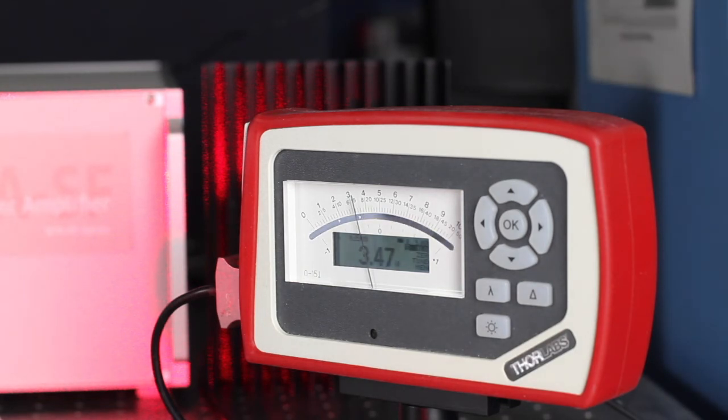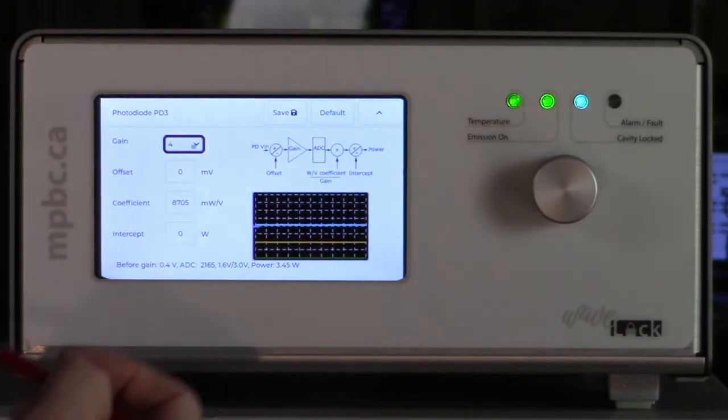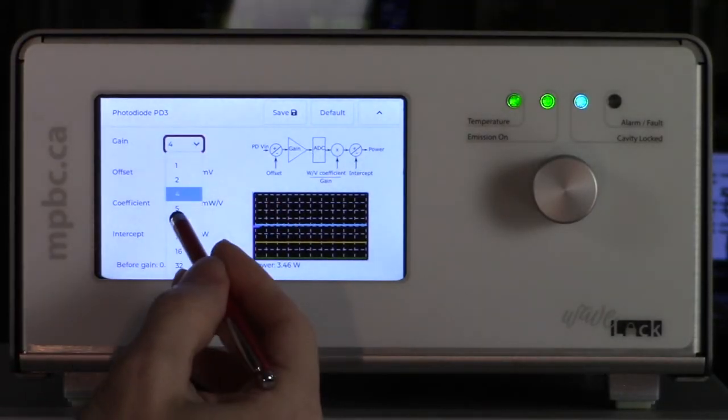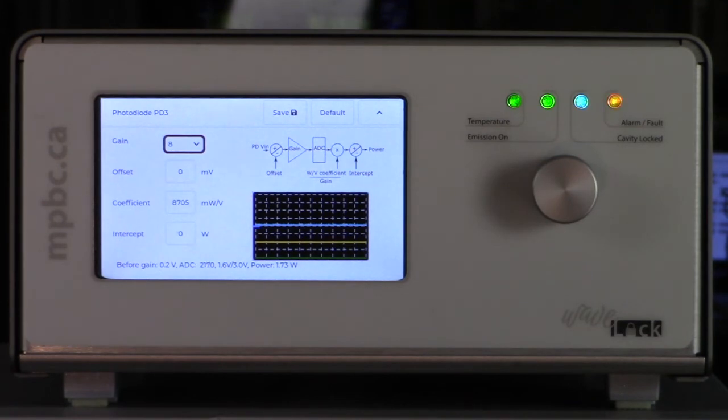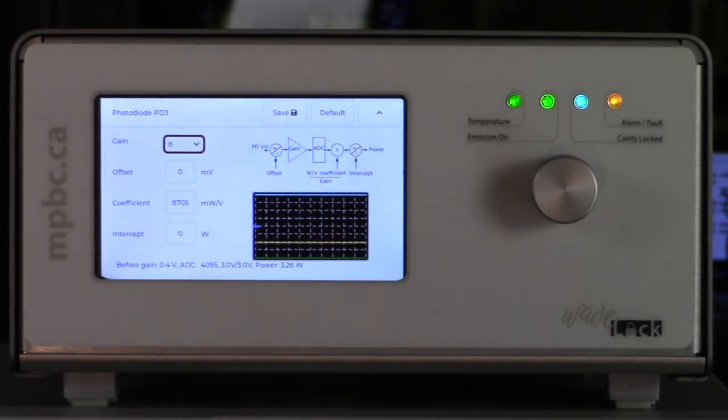Let's see what happens if we made a mistake, if we put too much gain at this input. I raise it to a gain of 8. Look at that. The blue line went to the very top and we get an alarm. That's because we were in over range.